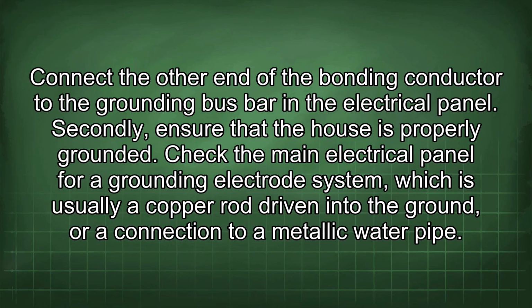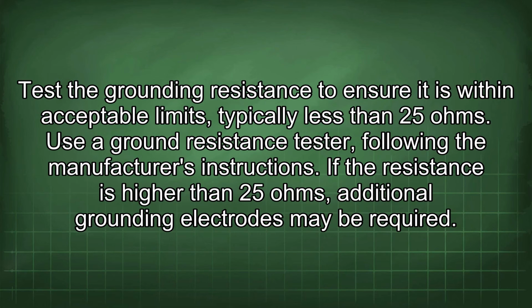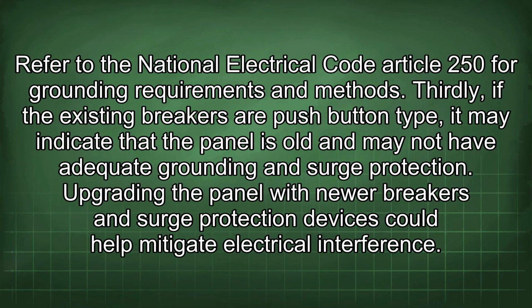Secondly, ensure that the house is properly grounded. Check the main electrical panel for a grounding electrode system, which is usually a copper rod driven into the ground, or a connection to a metallic water pipe. Test the grounding resistance to ensure it is within acceptable limits, typically less than 25 ohms. Use a ground resistance tester, following the manufacturer's instructions. If the resistance is higher than 25 ohms, additional grounding electrodes may be required. Refer to the National Electrical Code Article 250 for grounding requirements and methods.